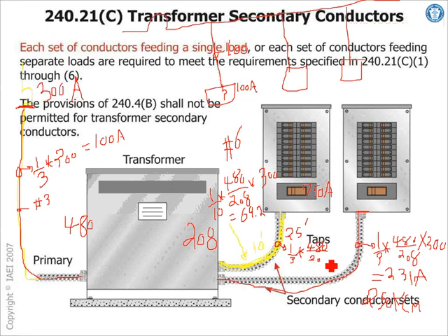divided by 208 multiplied by 300, which is, we already sized it, 300. So what did we say? It equals 231 amp, which in turn equals 250 kcm. So what's the difference between this 250 and this 250? This 250, guys, is the length from here to here plus the length from here to here is 25. This tap, the length from here to this equipment is 25.